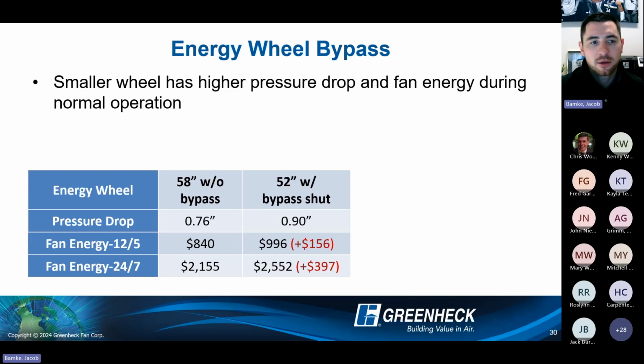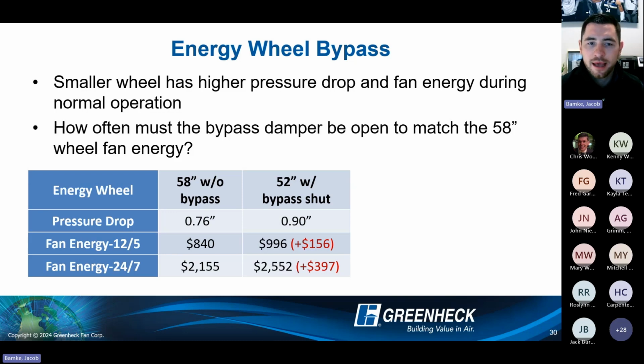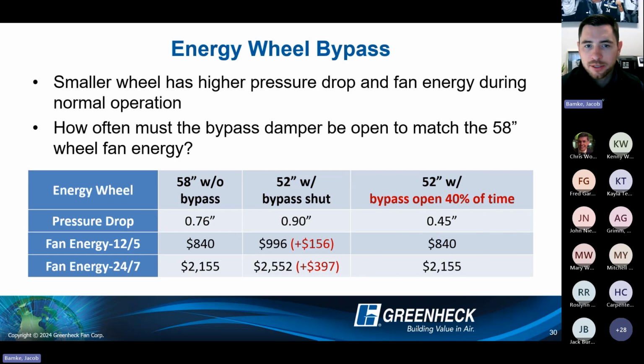So that always comes to the question of, well, how often do I have to have this bypass damper open to match the 58-inch wheel fan energy? And the answer to our study was about 40% of the time. That assumed a 50% pressure drop requirement. That is an assumption, not always true, but that is how we match the fan energy. Again, the other thing to keep in mind is how often does it have to be open to match that heating and additional cooling capacity required as well.